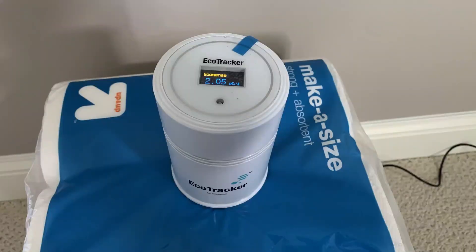We've got four eco trackers set up in the basement, so we'll have a pretty good idea. Even tonight I can call the customer and get a good idea of what we're getting into tomorrow — whether the radon levels are dropping or not, which will help us determine how much time we might spend here or if this is going to be a troubled system that we have to troubleshoot and figure out why it's not working.